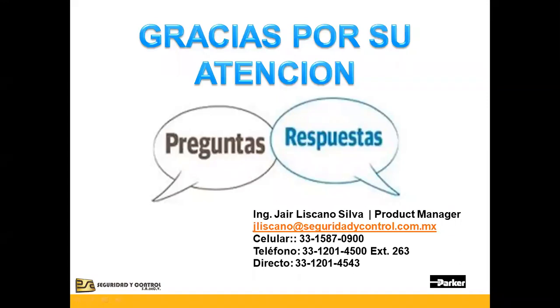Pregunta Luis García si solo manejan comunicación Modbus. En la serie AC10, sí, solamente tenemos comunicación Modbus, que ya viene integrada sin necesidad de pedirla. Esto nos permite tener redes de hasta 30 drives sin necesidad de pagar por un módulo de comunicación adicional, lo cual es importante cuando las potencias son relativamente pequeñas, ya que a veces el módulo de comunicación sale más caro que el propio drive. Con un solo par trenzado podemos controlar hasta 30 drives desde un Modbus Master, que puede ser un PLC de baja gama.